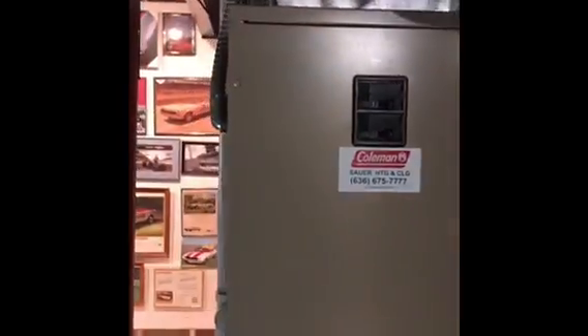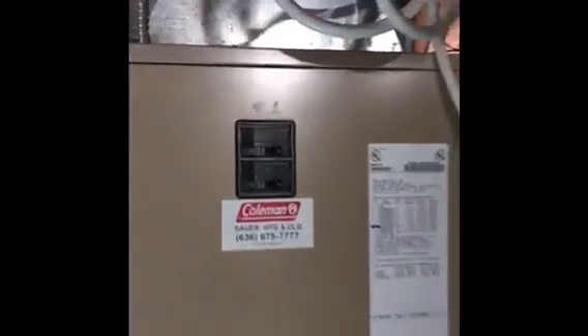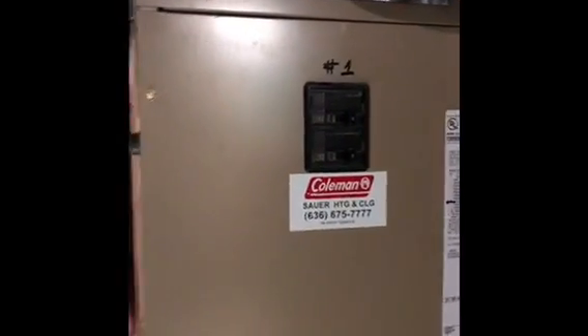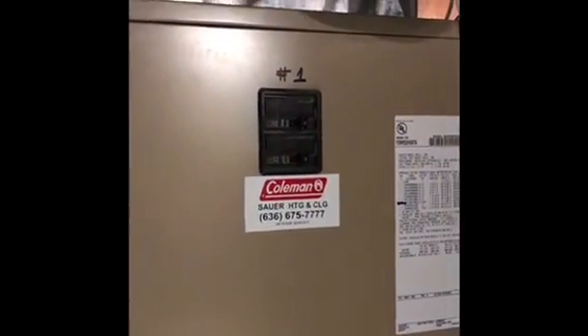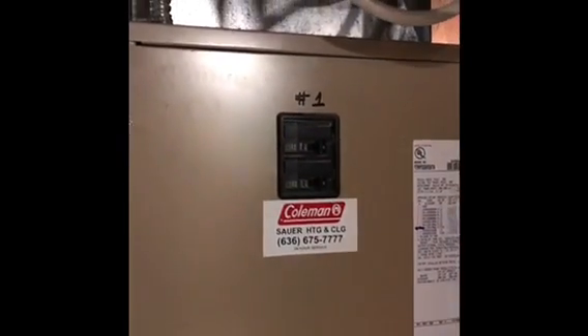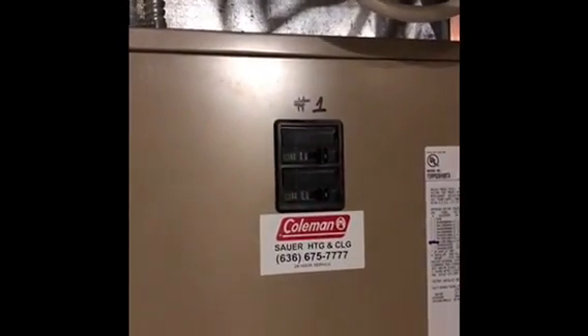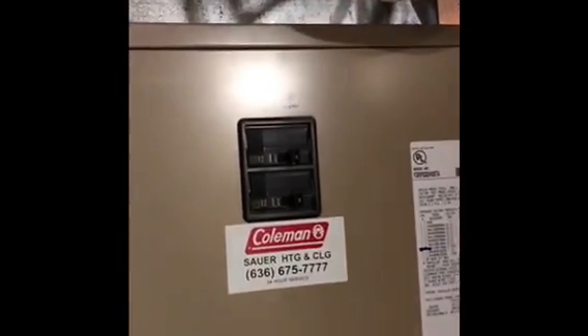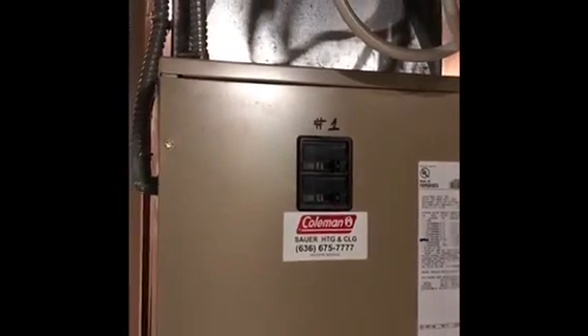All right, so looking at these 2 systems again, we're going to have to change the way that the electrical is run for the heating, of course, as well. So the system that's marked system number 1, this is going to be the 2-ton system that we install. We're going to have to terminate one of the wires that comes out of the panel. We're just going to run 60 amps of electrical to this system for the heat kit. And then the other system, we're going to have to run new electrical up through the ceiling, back over to the panel, which is over here on this side, so we can handle 90 amps of electricity for the heat.